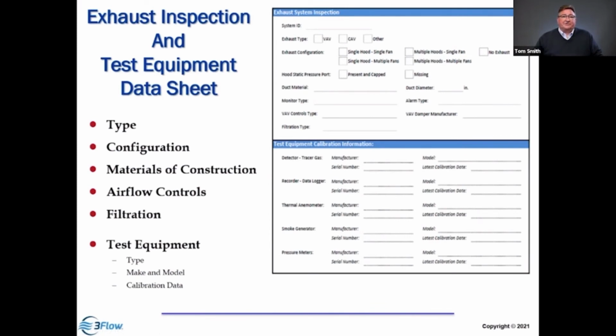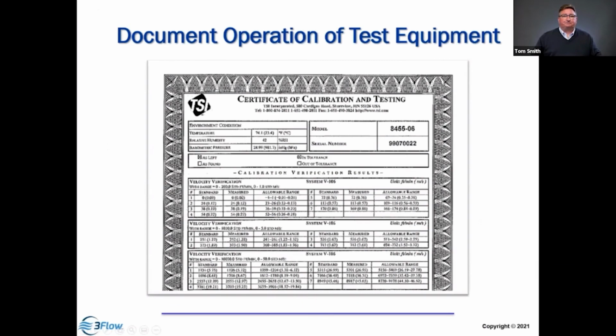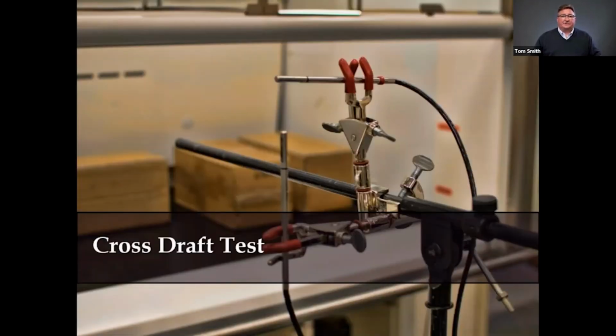We'll also take a look at the equipment that we're using. What is the instrumentation that's being used to conduct the test? Record the manufacturer, the serial number, the model, and the last date of calibration. All equipment should be calibrated at least annually and certainly in accordance with all the manufacturer's specifications. Some instrumentation, like the tracer gas detector, needs to be tested and calibrated daily. So we need to confirm the calibration of the equipment and make sure everything's functioning properly. Record and report these data sheets so that we have the right information to confirm that the data was correct at the time we collected it. Save a lot of issues.